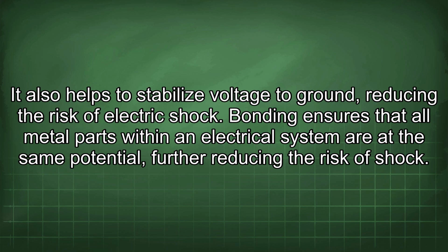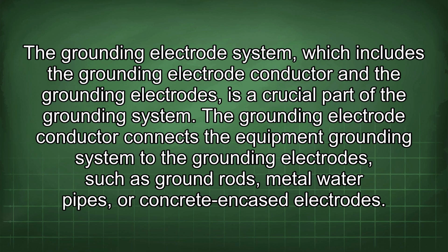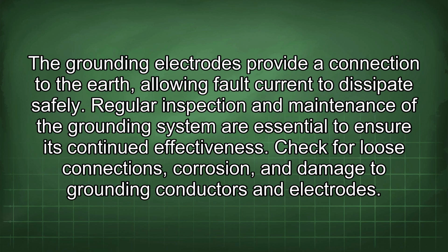It also helps to stabilize voltage to ground, reducing the risk of electric shock. Bonding ensures that all metal parts within an electrical system are at the same potential, further reducing the risk of shock. The grounding electrode system, which includes the grounding electrode conductor and the grounding electrodes, is a crucial part of the grounding system. The grounding electrode conductor connects the equipment grounding system to the grounding electrodes, such as ground rods, metal water pipes, or concrete encased electrodes. The grounding electrodes provide a connection to the earth, allowing fault current to dissipate safely.